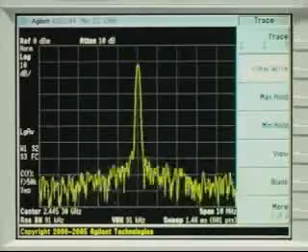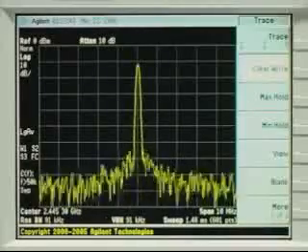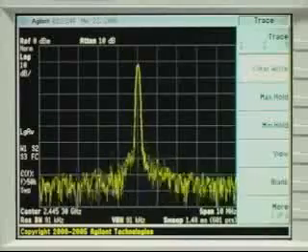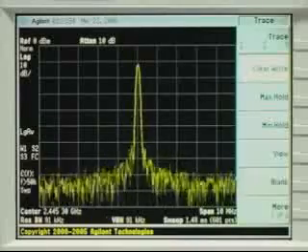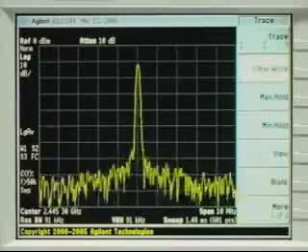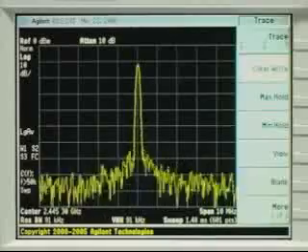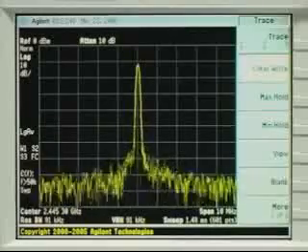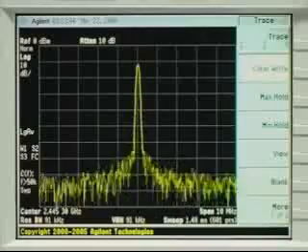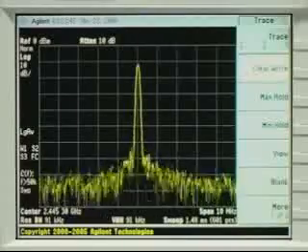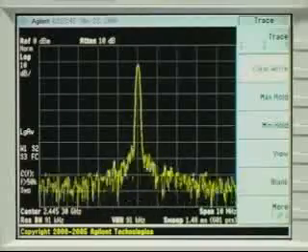The challenge for both instruments is to see how quickly they can characterize the behavior of this signal so that the user can identify the problem. Both the PSA and the RSA 6100A have been set to a 10 MHz span, both with the same center frequency of 2.4453 GHz, and both have a similar resolution bandwidth.